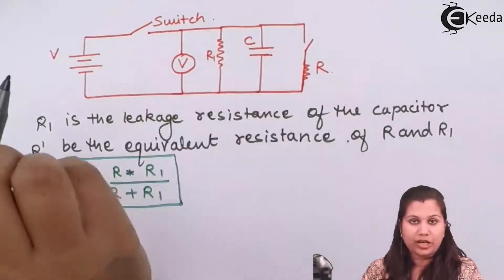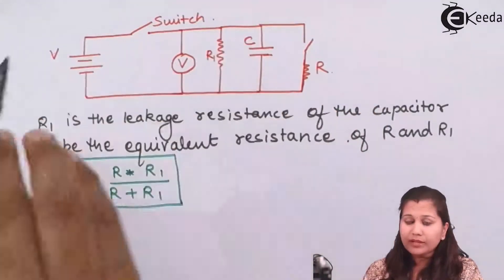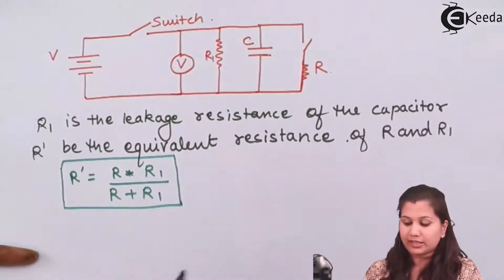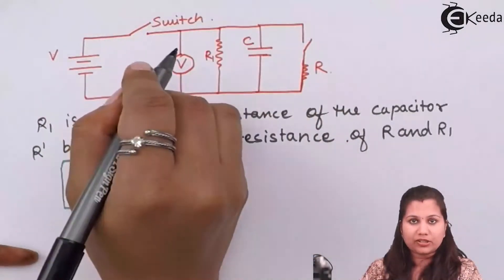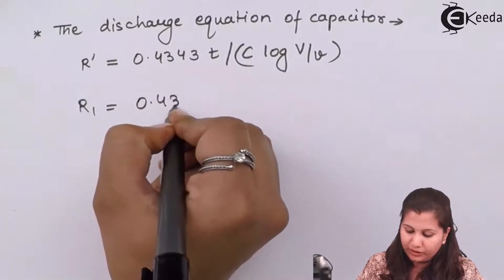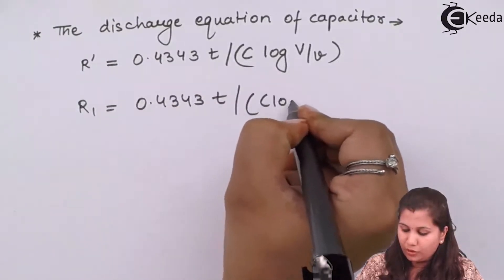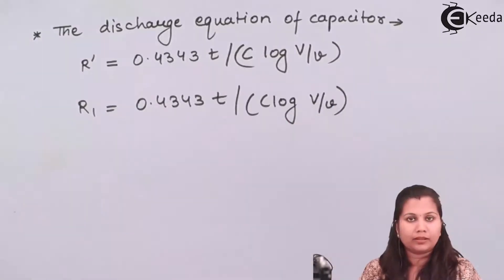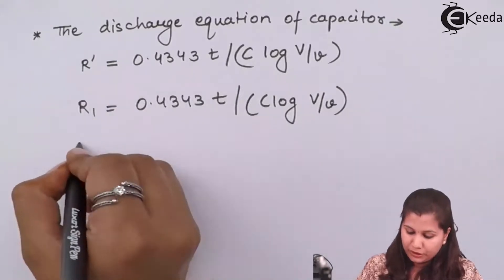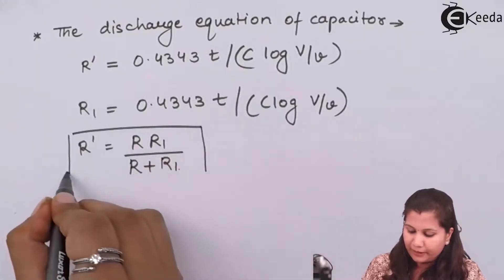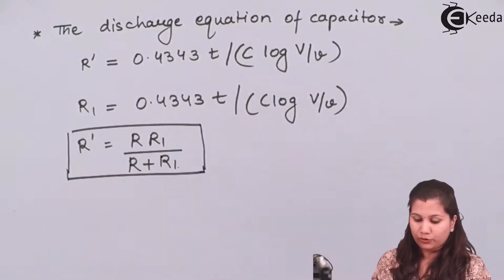In the second case, both switches are open and the capacitor discharges through the leakage resistance R1 only. The discharge equation changes to: R1 equals 0.4343 T divided by C times log base 10 of capital V by small v. From these two equations together with R' equals R times R1 divided by R plus R1, we can obtain the value of the leakage resistance of the capacitor and the unknown resistance.